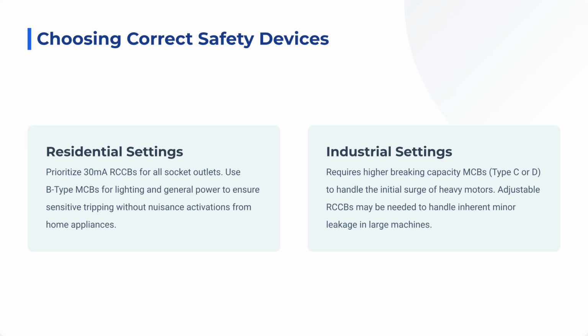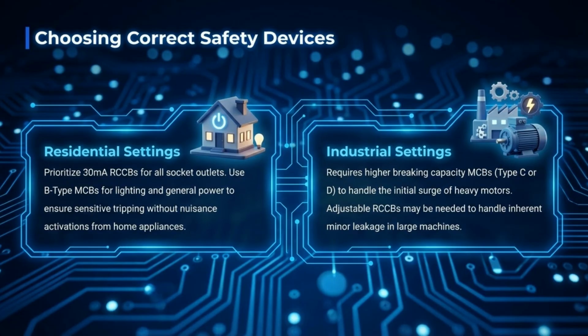For residential use, prioritize 30 milliamperes RCCBs for sockets and B-type MCBs for general power. Industrial settings need higher capacity MCBs, such as Type C or D, to manage the surge from heavy motors, along with adjustable RCCBs for minor leakage.